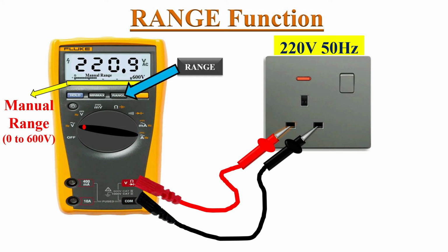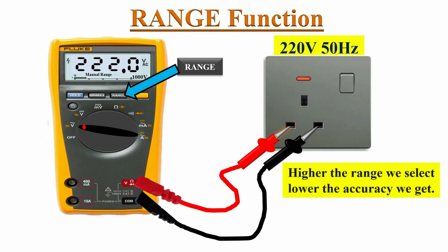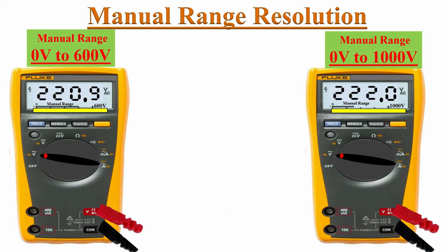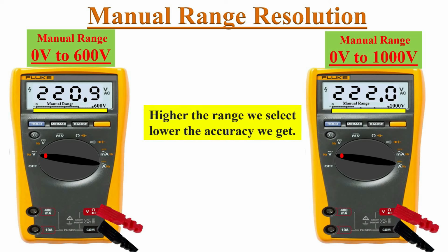If we push this range button again, then the meter will enter the next range of 0 to 1000 volts. But if we observe the reading here, the meter reads the measurement as 222 volts instead of 220 volts. The meter reads 220.9 volts in the 0 to 600 volts range and 222 volts in the 0 to 1000 volts range. It is to be noted that the higher the range we select, the lower the accuracy in reading.